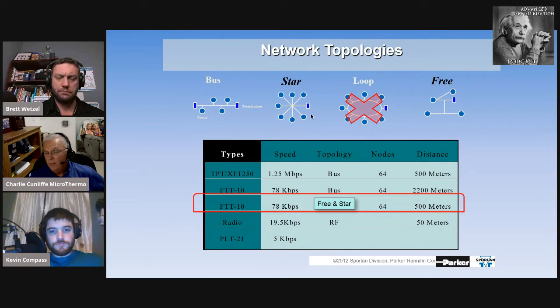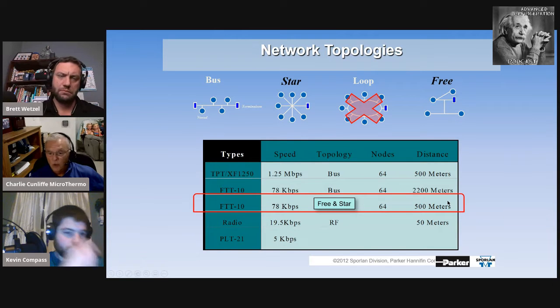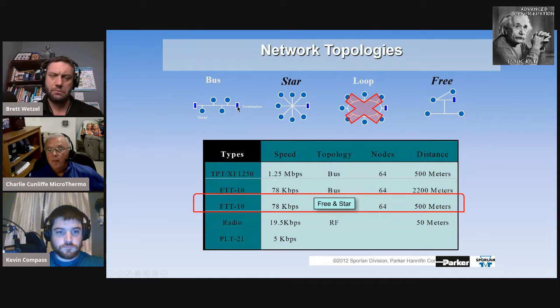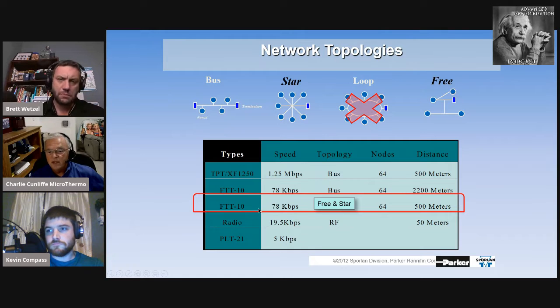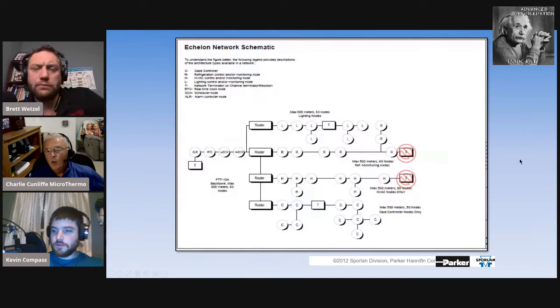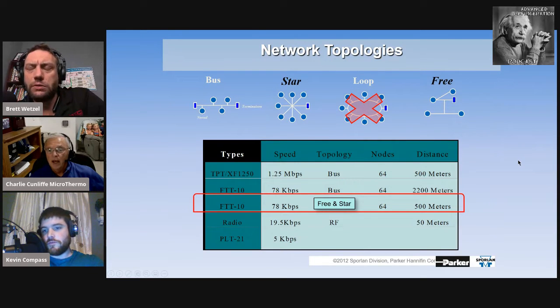If you go into a startup and see that the electrician or communication contractor has wired the network as one gigantic daisy chain with a terminator on the end, run away—it's not going to work. That's an Echelon violation. I have used bus topology in extremely large commercial applications, where speeds reach the mega range, but for supermarkets we stick with FTT-10 in either a star or free configuration. Jump in anytime if you have a question, but I wanted to give you this background before we go into a live store.